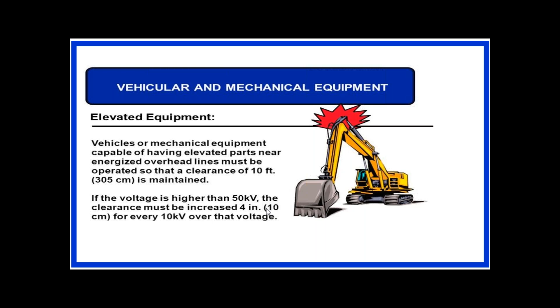If the voltage is higher than 50 kV, the clearance must be increased 4 inches for every 10 kV over that voltage. So up to 50 kV, you have to keep a distance of at least 10 feet, and if it is 60 kV, then 10 feet plus 4 inches, then 70 kV, so 10 feet plus 4 inches plus 4 inches, so 10 feet and 8 inches, and likewise. So you have to keep the distances as per the standards.